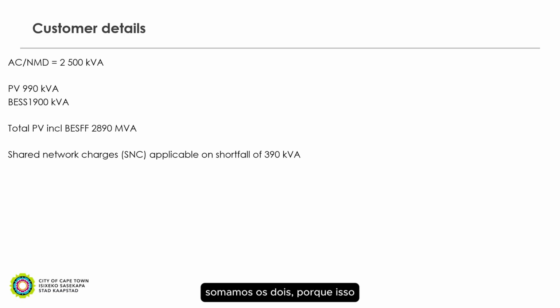And for that reason, we basically add them together because that will be the total impact we will see from the network. So in this particular case, for example, the total that wants to be installed is 2.89 MVA versus a 2.5 MVA NMD. So in this case, there is a shortfall of 390 kVA, and therefore the customer would need to pay what we call network charges to allow him to install the system, or he can reduce the battery energy storage system by that amount to be able to continue with the installation.